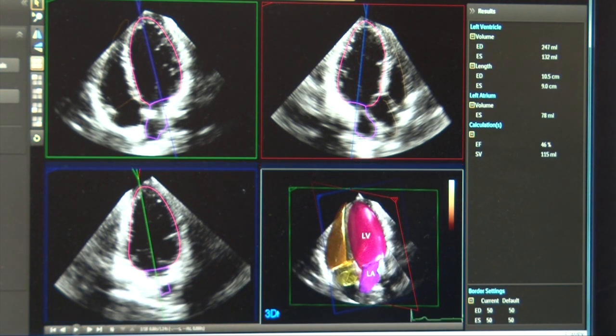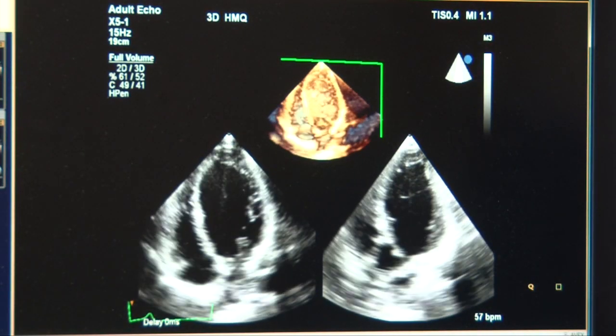In terms of premium ultrasound, Philips introduced anatomical imaging for their EPIQ system as a commercial launch here at RSNA. With anatomical imaging, they take a 3D transducer and capture an entire volume. Instead of being dependent on the user's experience in scanning and knowing exact angles to image a heart or liver, when you collect the 3D volume you have a box of data and the system will automatically segment everything to the exact views that physicians need.